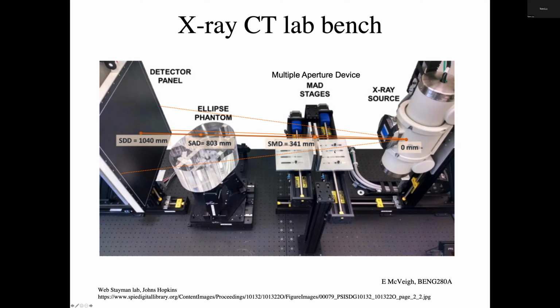All the low energy X-rays get absorbed, and the higher ones come through. This is a really neat system in that it has a grid of these pre-filters so that you can modify basically the Fourier structure of the beam before it hits the patient. And then this is the phantom, and you just rotate this phantom, and that simulates the whole thing rotating around.